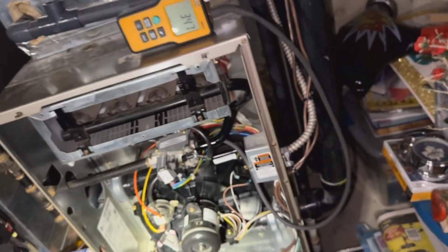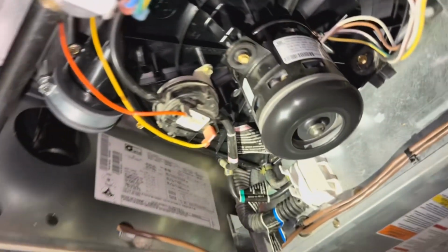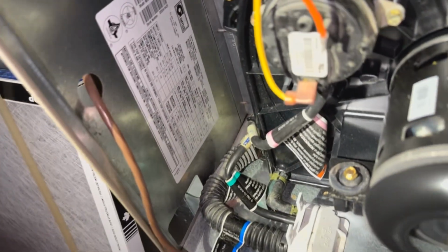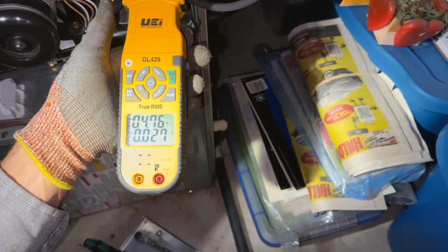So yeah, give a shot of the reading plate. See that information that we get to look at. It gives us the amp draw on the unit, Delta T, temperature rise. Let's see how much you're drawing on this one, Joe. So the 138.7 is degrees Fahrenheit of supply air coming to the house to heat everything up, which for Carrier, not so bad. Amp draw is coming in at 4.76 amps.